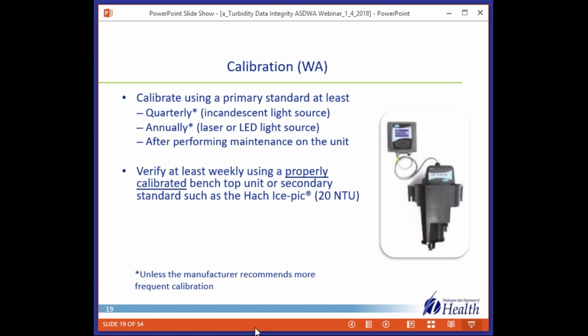Calibration and verification are critical operations for turbidimeters. In Washington State, online instruments must be calibrated using a primary standard at least quarterly if they have an incandescent light source, and annually with a laser or LED light source, unless the manufacturer recommends more frequent calibration. And must be calibrated after performing maintenance on the unit. So maintenance such as cleaning the photocell or changing the lamp can affect readings.